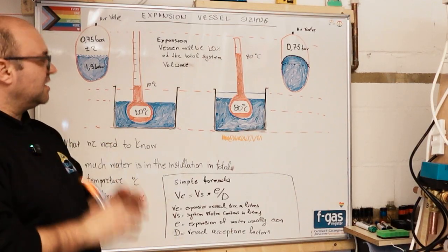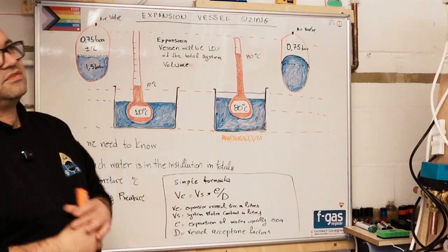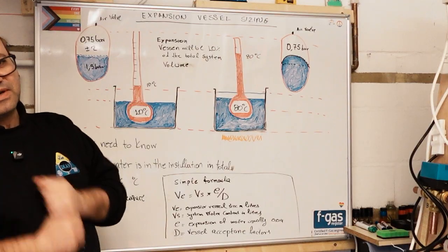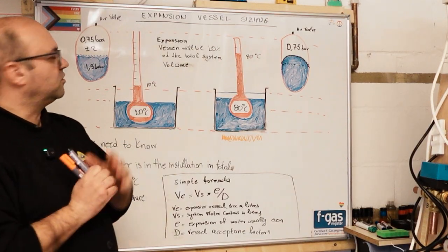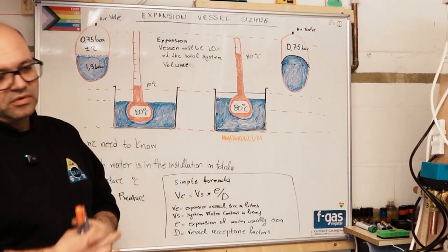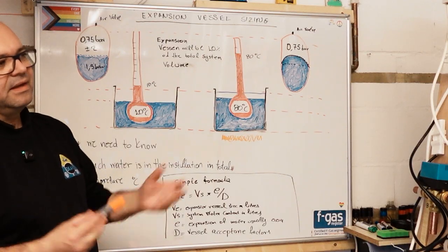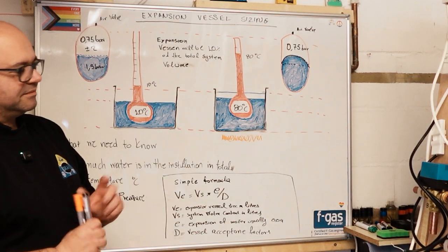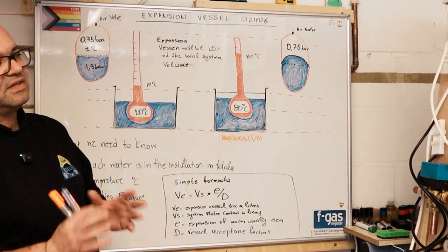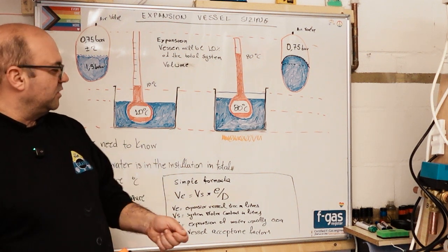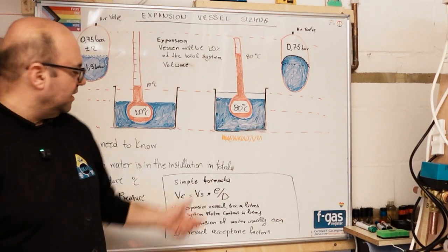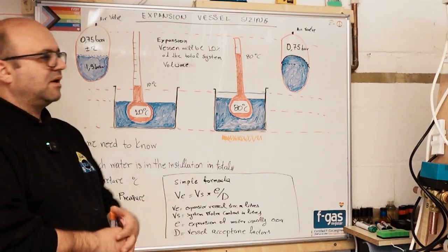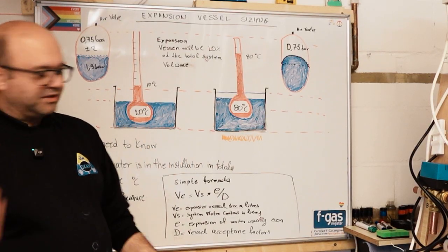The very general rule of thumb to calculate what size of expansion vessel we need, let's keep it very simple, is 10% of the total volume of the water. How to calculate the water in the system? The very scientific way is to use a water meter when we fill up the system when it's empty. Okay, we don't do that. You can calculate, for example, roughly about 10 liters per radiator on average.